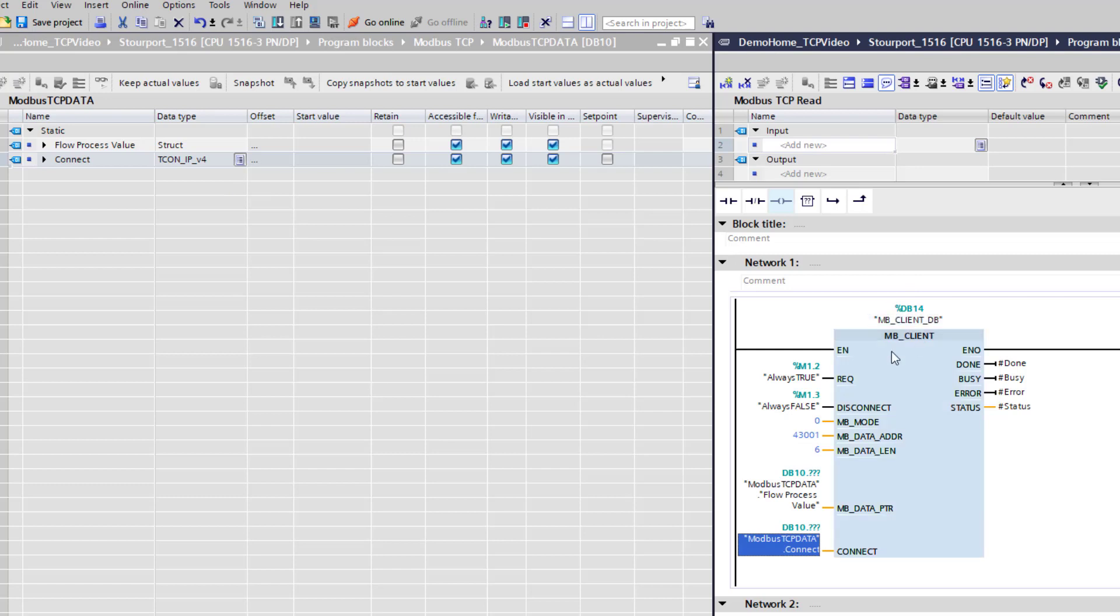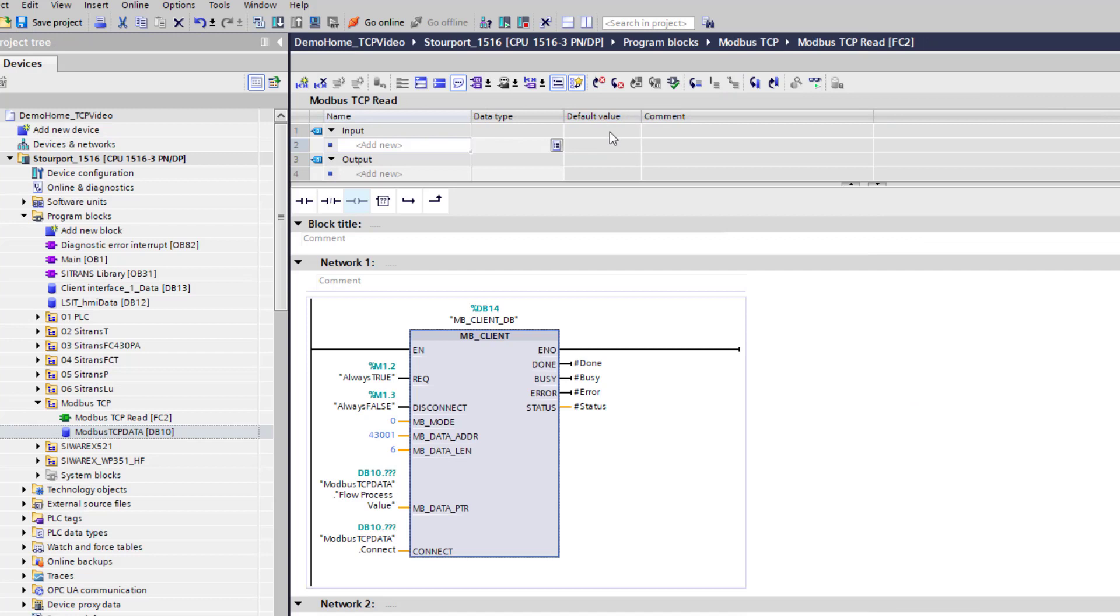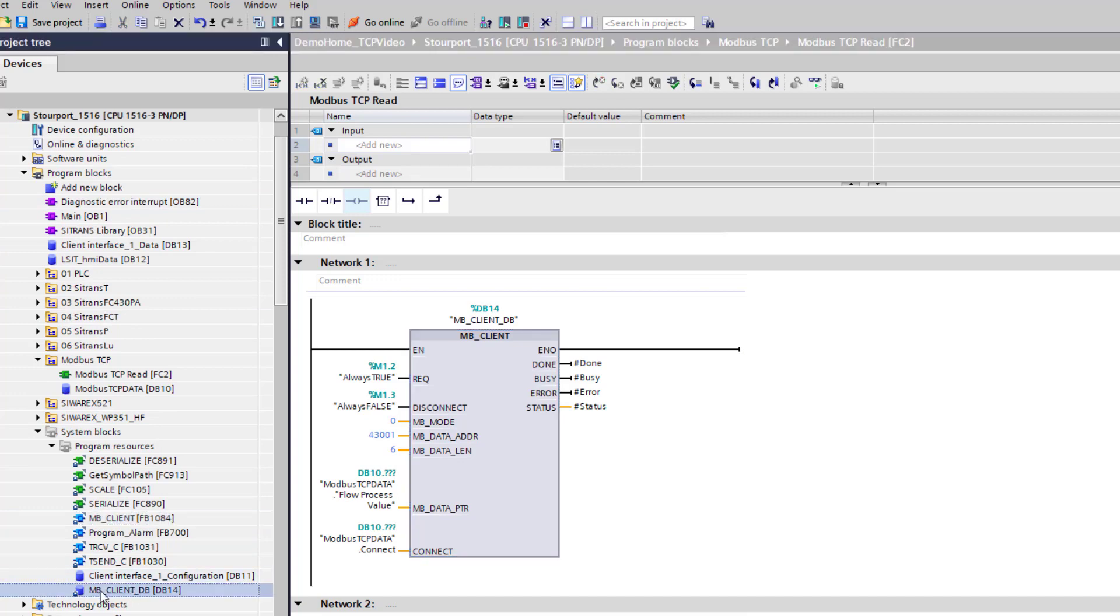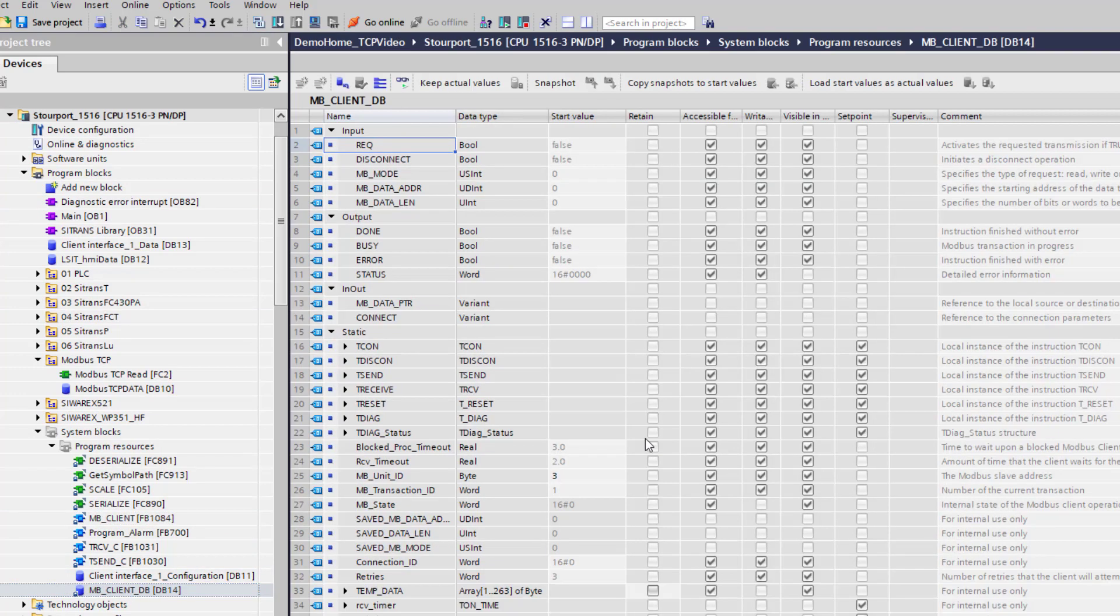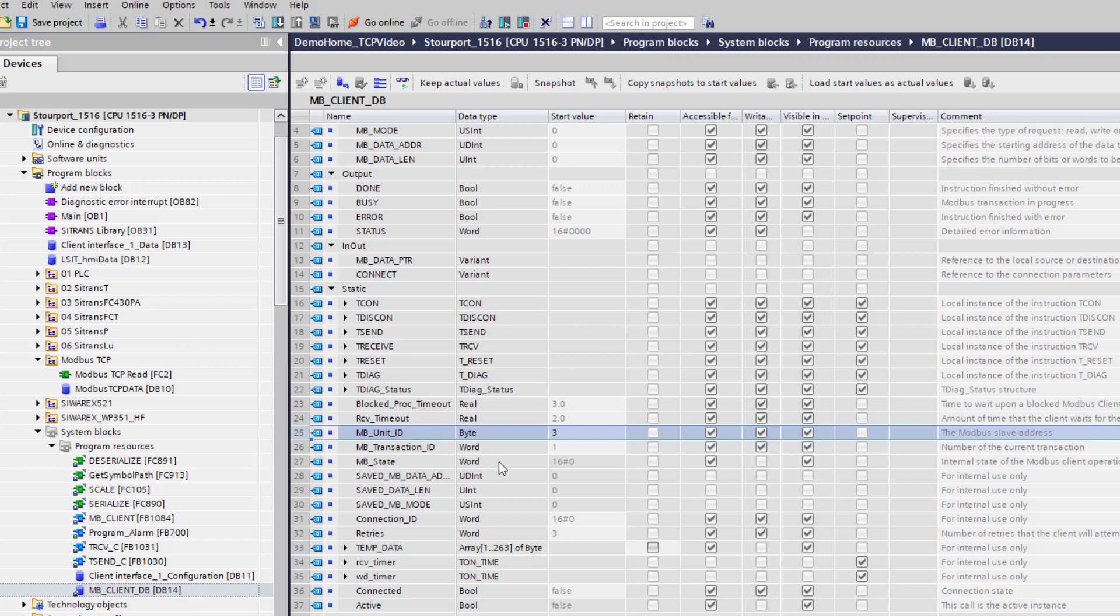One thing we need to do is we have told it how to connect to the gateway, but you might have multiple Modbus 485 instruments connected to the gateway. So for every separate device you will have to have a separate data block. So you can copy this if you are doing multiple reads to the same device, but as soon as you add another Modbus slave then we need to add another MB client DB. And that can be a little bit tricky where that is stored. So if you go to system blocks and then under here you will see the data block MB clients which is know how protected. But we do need to change something. I have already done it on this particular one but you can see here.